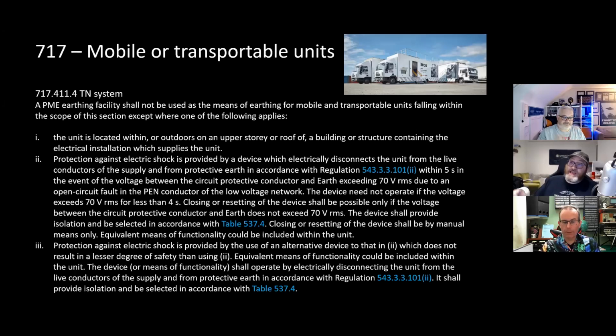We need to be mindful of it. So the approach here is, if a PME facility, it should not be used as a means of earthing unless it falls within the scope of this section, except where it's located within or outdoors on an upper story or roof, a building or structure containing the installation which supplies the unit.